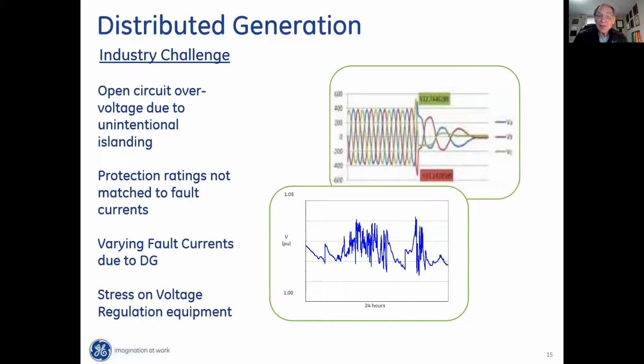But when modeling the grid for a short circuit study, we typically only look at the source side contribution to the fault, not the load side contribution. As the penetration of distributed generation grows, the load side contribution becomes more significant and needs to be taken into account. The challenge is that this load side contribution varies, because the sun isn't always shining and the wind isn't always blowing, so fault currents vary based on the intermittency of distributed generation.